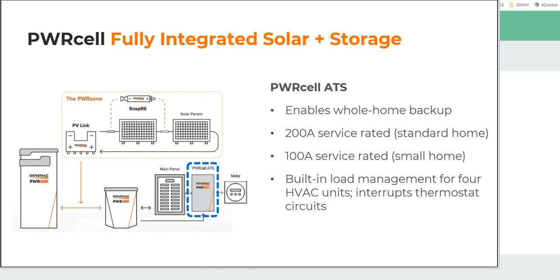What's unique about this is it has built-in load management for 4 HVAC units. So inside this device, we have switches that can turn on and off thermostats. So we have low voltage switching. If you want to run thermostat wires out there, we can control HVAC units right from that automatic transfer switch. So what that lets us do is take those loads and put them out of the way during an outage. We can bring them back on as needed, one at a time, but initially it lets us shed them so that we can protect the inverter from overload during an outage.